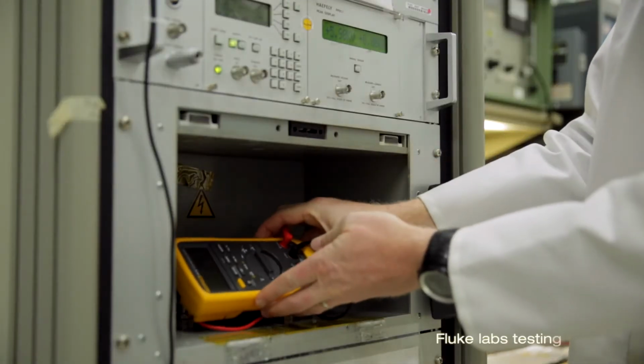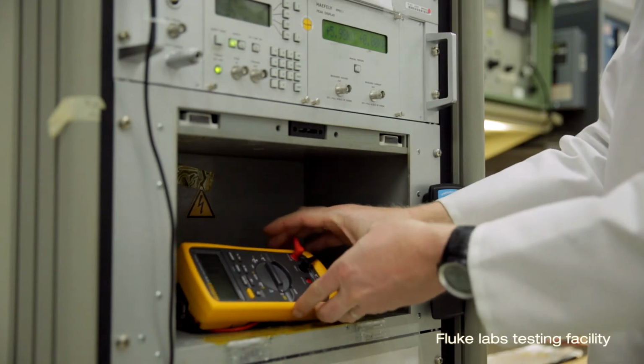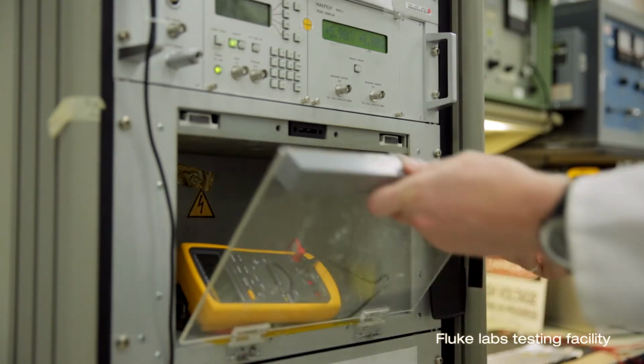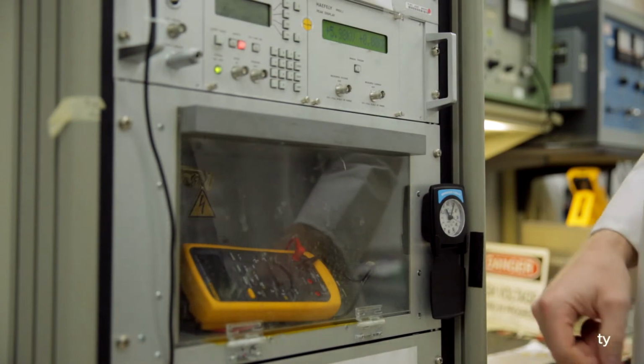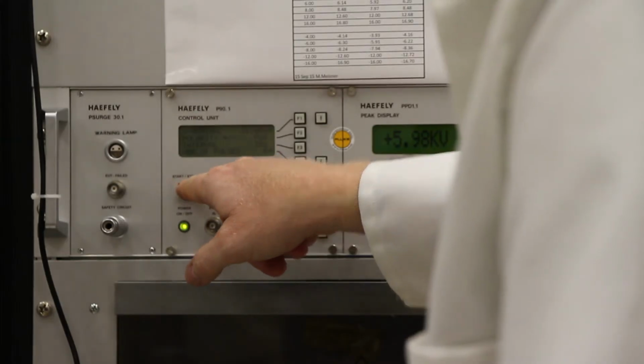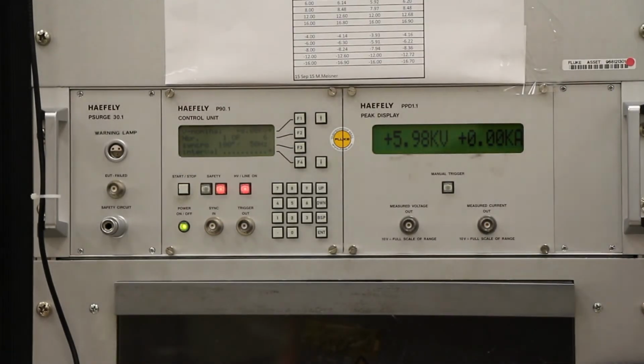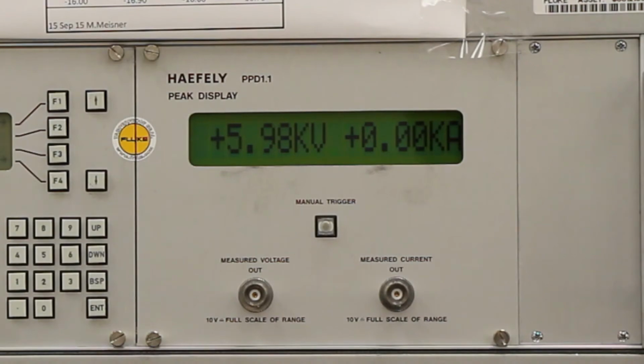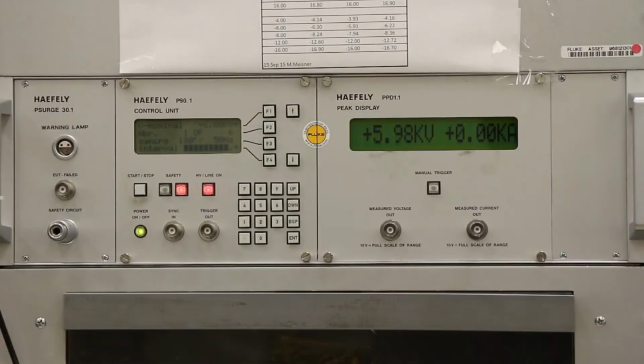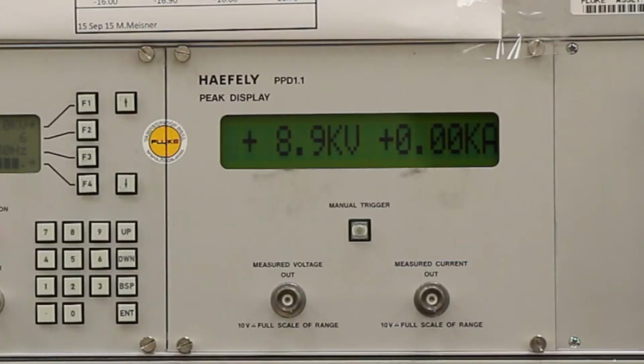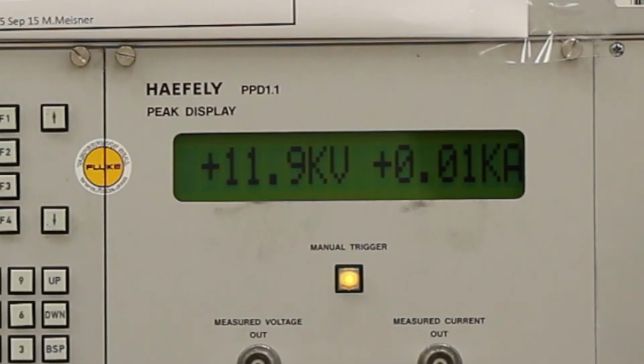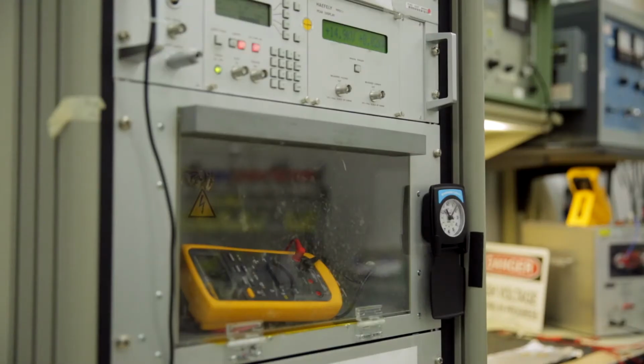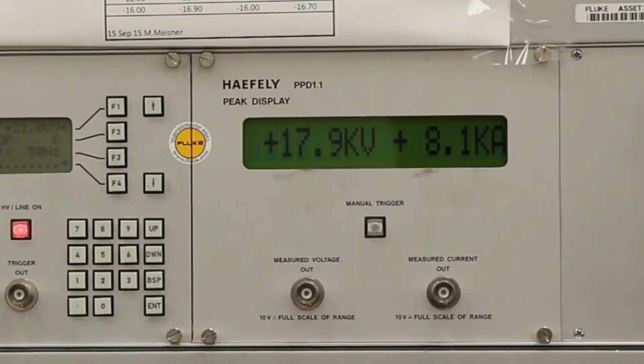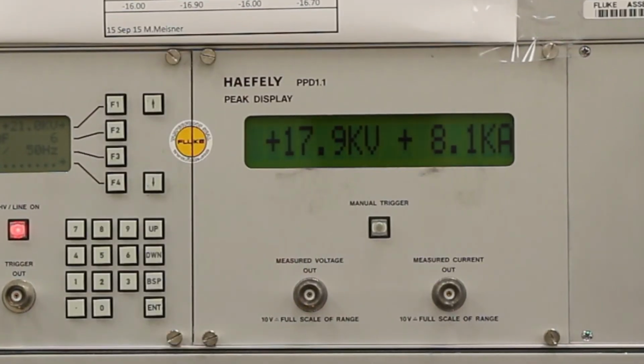A special test machine is used to generate the overvoltage transient and fault current as defined by national and international standards. In this short trial, we have programmed our test machine here at Fluke Labs to increase the transient voltage in steps until the test instrument fails. 6,000 volts, 9,000 volts, 12,000 volts, 15,000 volts. This test instrument finally failed at about 17.9 kilovolts, more than double the minimum of 8 kilovolts.